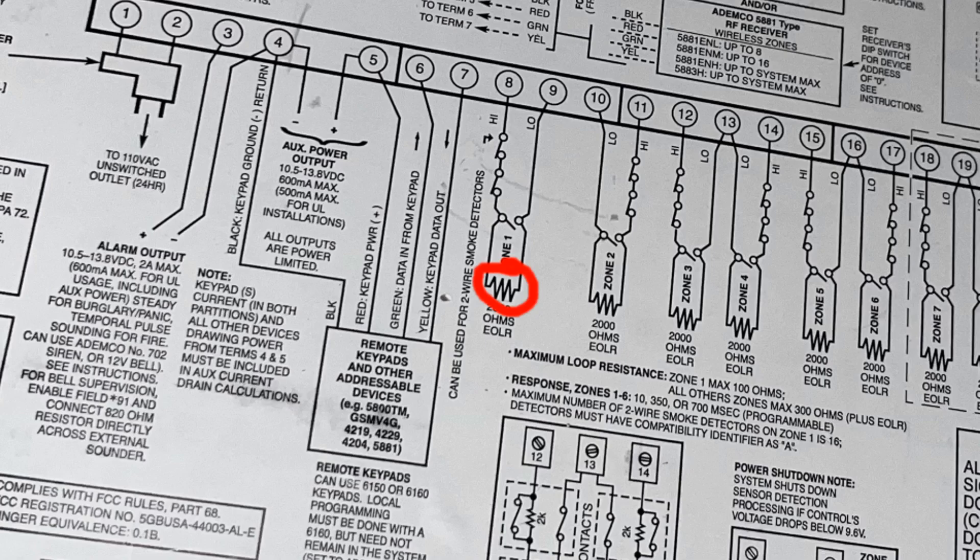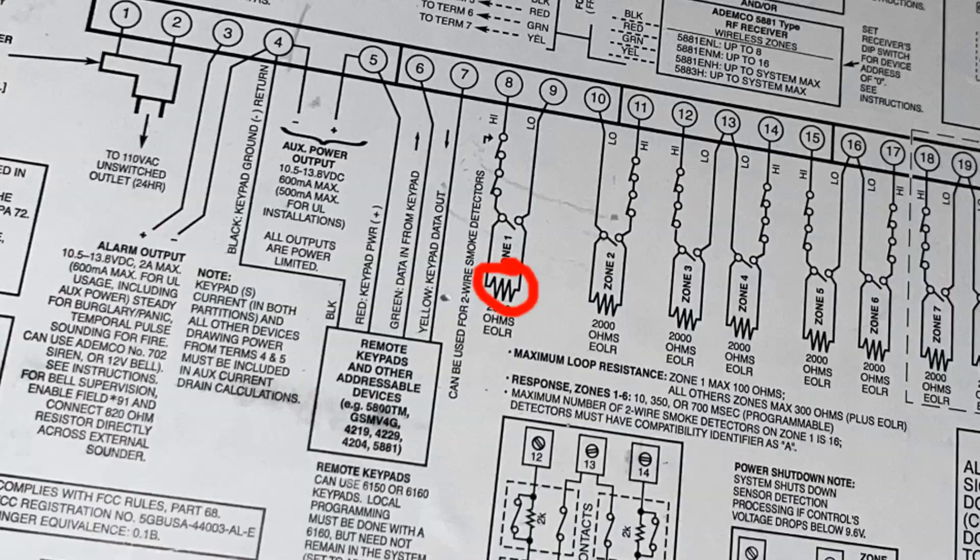So, like, in this case, for the smoke detector, if we take off the smoke detector head, the panel will detect a difference in resistance and will go into trouble. And same thing with any other zone that's, like, normally open. If you were to, like, cut the wire to a zone, the panel is going to notice that.